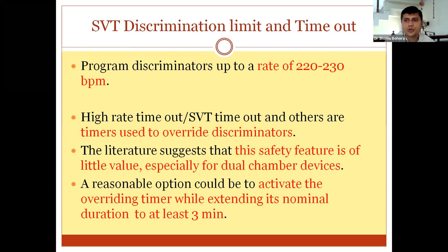That is programmable. Lastly is timeout. Even if you detect SVT and it goes at a higher rate, after a certain period of time the device can shock. That's very important. And you can program it around 3 minutes. So, the summary to avoid an inappropriate shock in these circumstances: first, prevent the recurrence of this atrial arrhythmia. That is rule number 1. Second is optimize your AV nodal blockade so that the ventricular rate doesn't go fast even if there is an atrial arrhythmia. Third, you can detect.